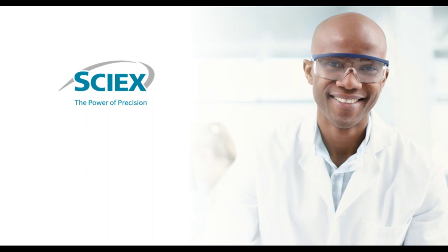But from my experience, we only need to calculate experimental pI once for IND. So when we have used CZE approaches or ion exchange approaches, we just run it on IEF once. And what's nice is on the PA800 Plus system, you can run them both right there. So you run it once for your IND, then you move back to your control method, which could be a CZE approach.